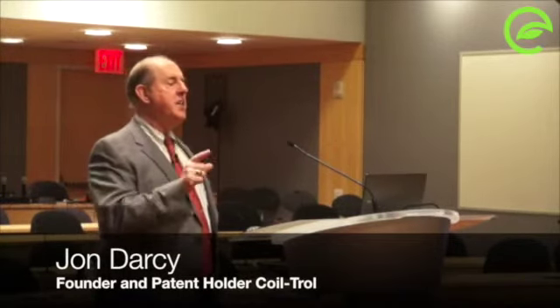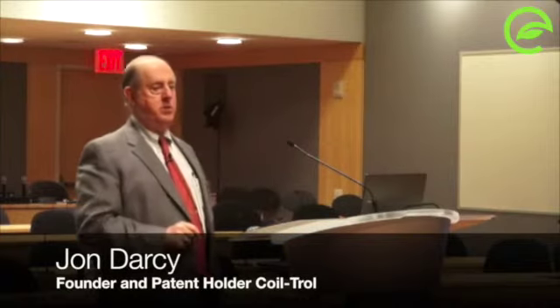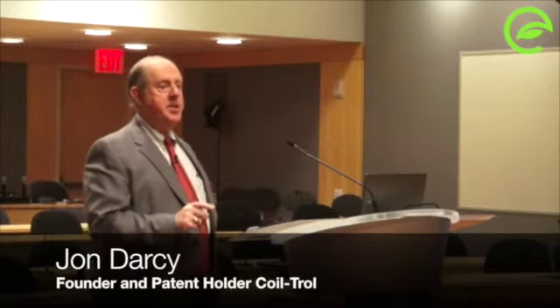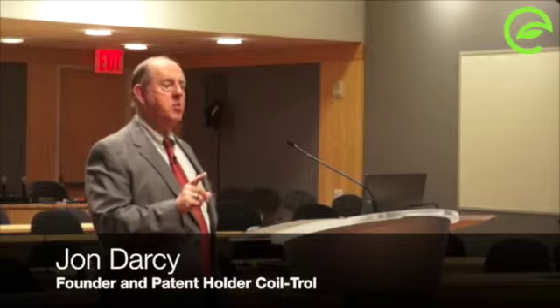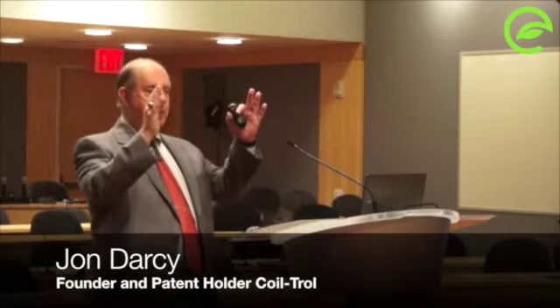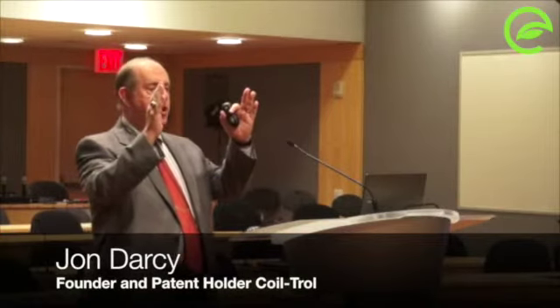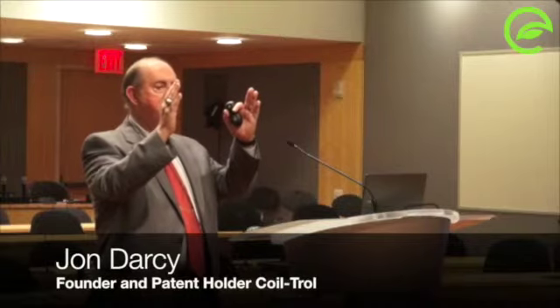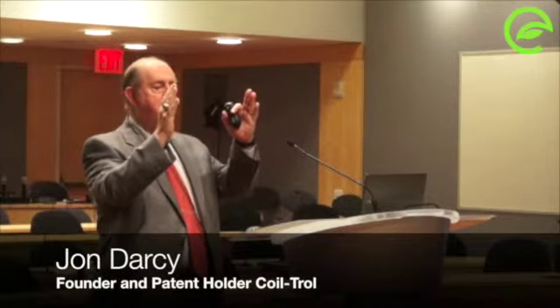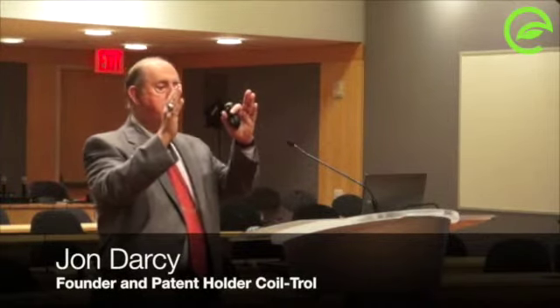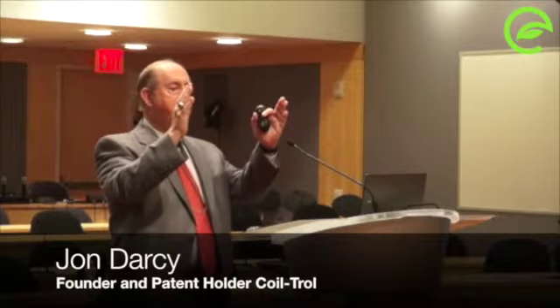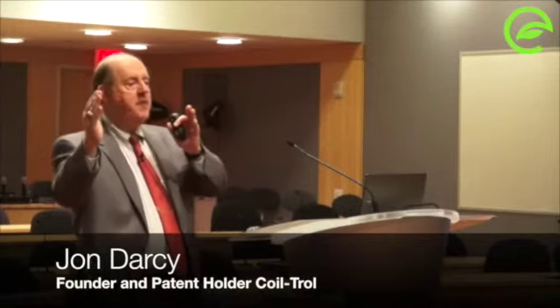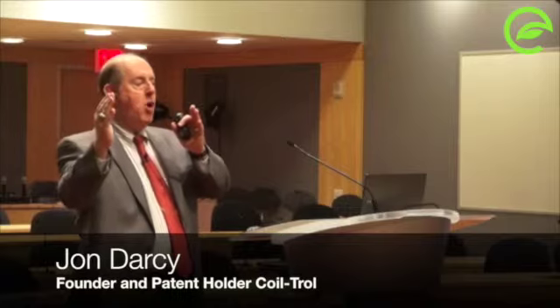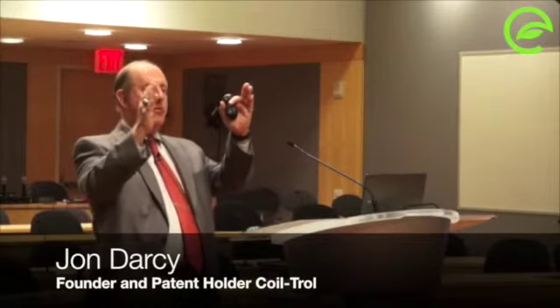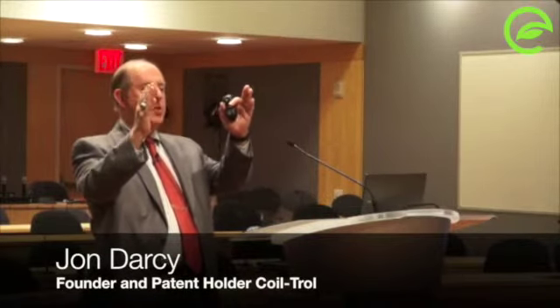You didn't see this problem when you had pneumatic controls. And the reason you didn't see it is you only had proportional only controls, which means you had a throttling range. That means if it was set at 55 and you had a 5-degree throttling range, the discharge air had to go to 52.5 for you to close the valve, and it had to go to 57.5 to fully open the valve. And that was the throttling range of the system, 52.5 to 57.5.